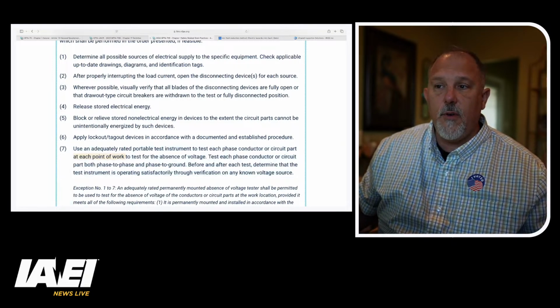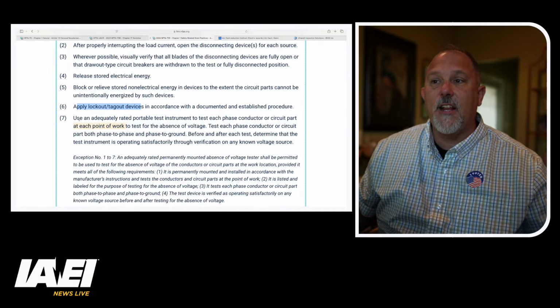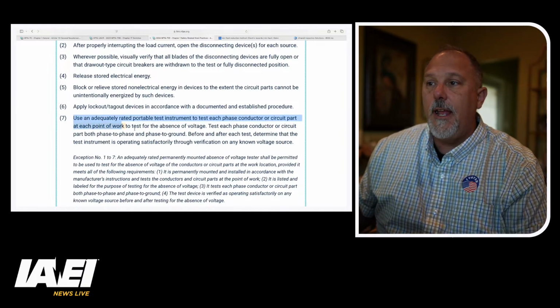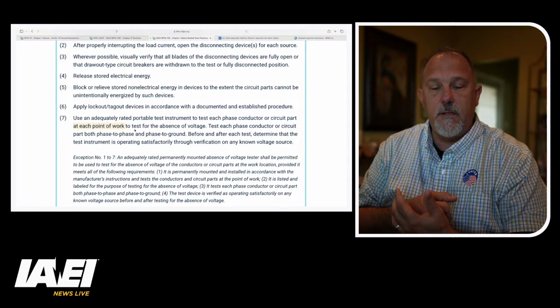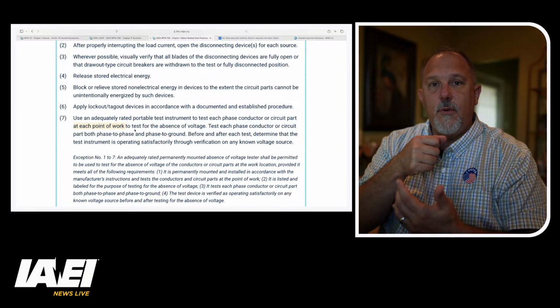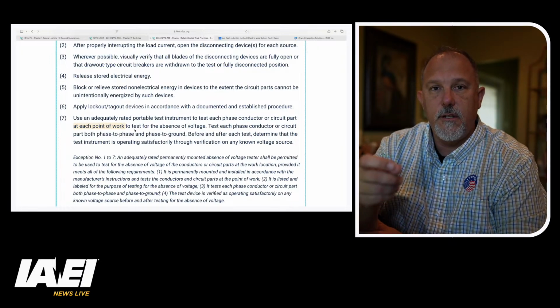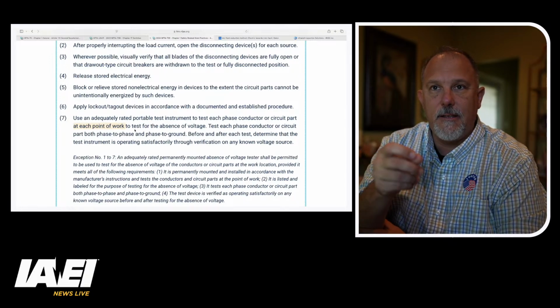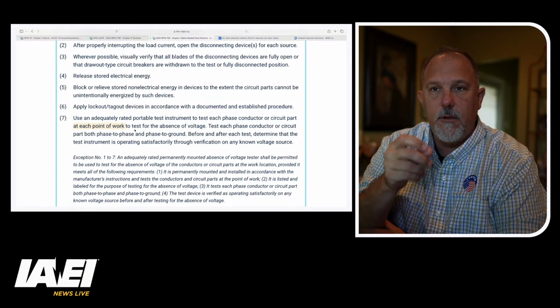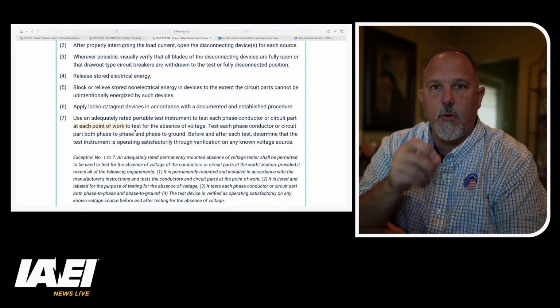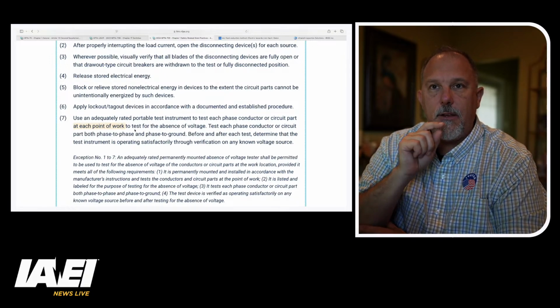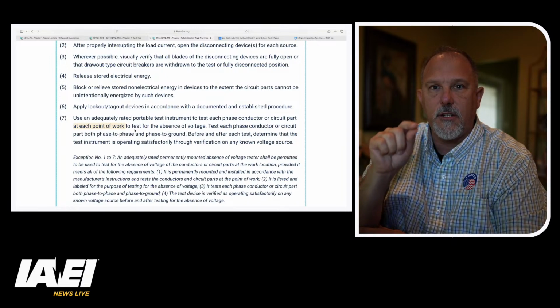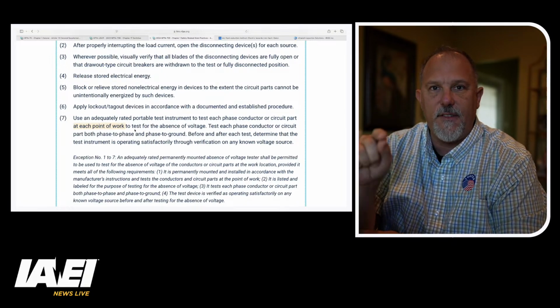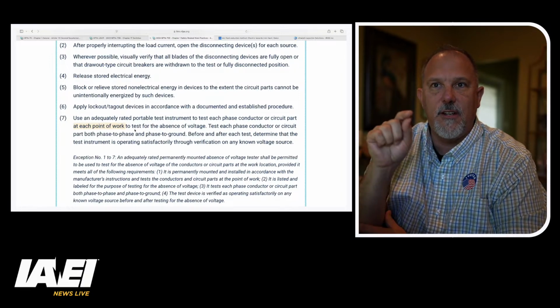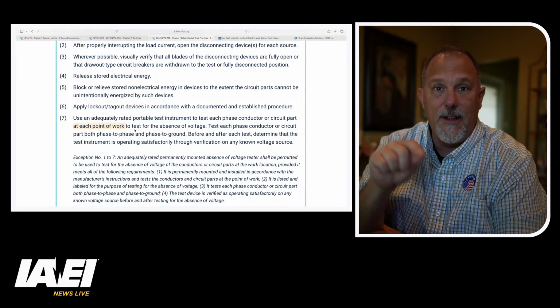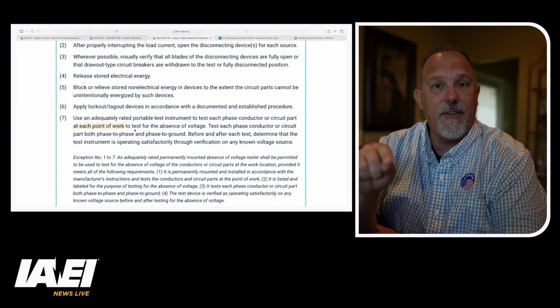I am going to apply a lock and tag out device, and then I got to go back down to that switch, and I need to take a test instrument, and I need to measure the voltage at that non-fused disconnect switch with the door open. I cannot say that I have achieved an electrically safe work condition until I've verified absence of voltage, and I have to consider it is energized until I verify. So is that energized work?